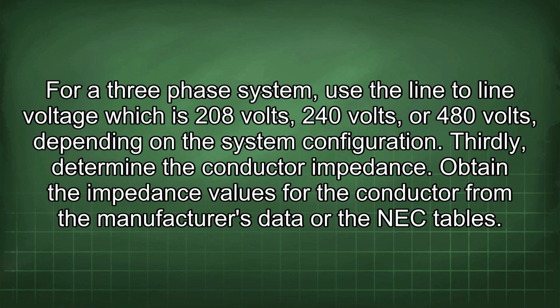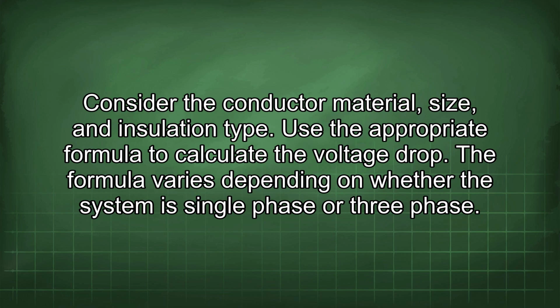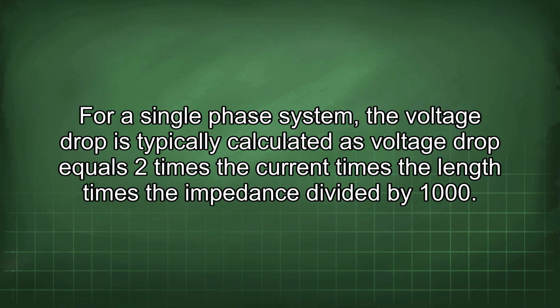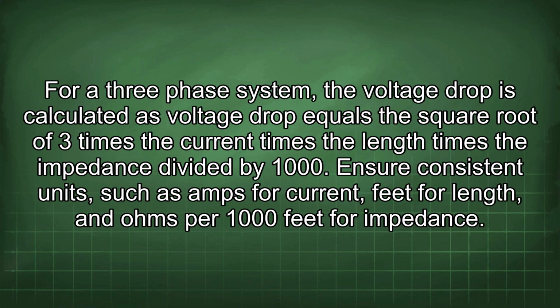Obtain the impedance values for the conductor from the manufacturer's data or the NEC tables. Consider the conductor material, size, and insulation type. Use the appropriate formula to calculate the voltage drop. The formula varies depending on whether the system is single-phase or three-phase. For a single-phase system, the voltage drop is typically calculated as voltage drop equals 2 times the current times the length times the impedance divided by 1000. For a three-phase system, the voltage drop is calculated as voltage drop equals the square root of 3 times the current times the length times the impedance divided by 1000. Ensure consistent units, such as amps for current, feet for length, and ohms per 1000 feet for impedance.